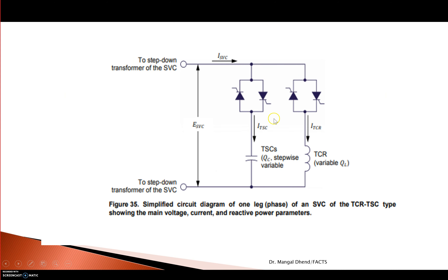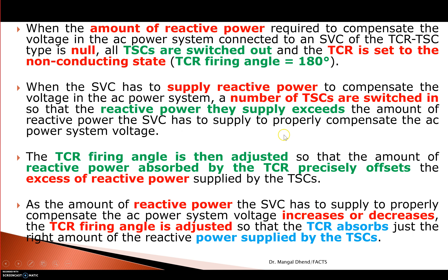For one leg, the total SVC current I_SVC equals I_TSC minus I_TCR by phasor addition, since TCR absorbs and TSC supplies. When TCR firing angle is 180 degrees, TCR output is 0. When TCR firing angle is 90 degrees, TCR output is maximum. Like that, you can control any amount of power — absorb or supply into the system.